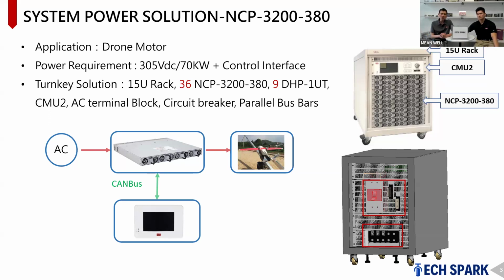So our solution is that we don't have one single power supply that is 70 kilowatts. We were proposing the 15U rack, 19 inch rack, and putting 36 NCP 3200-380 units inside the rack, which gives 70 kilowatts and 305 VDC to support the application.